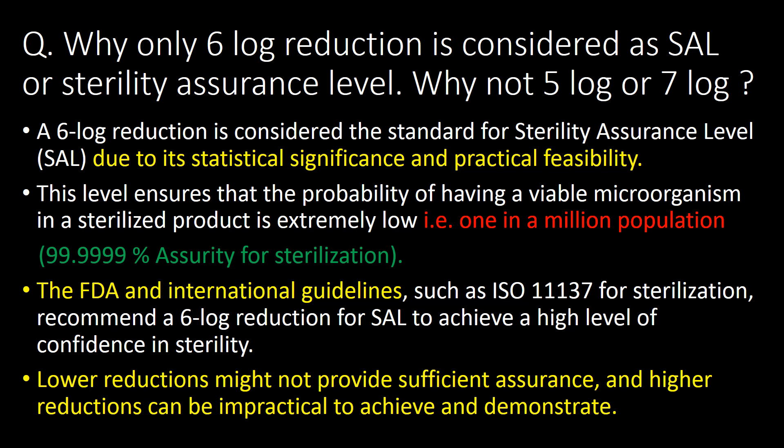The third point is guideline reference. The FDA and international guidelines such as ISO 11137 for sterilization recommend 6 log reduction for sterility assurance level to achieve a high level of confidence in sterility. The fourth important point is that lower reductions might not provide sufficient assurance, and higher reductions can be difficult to achieve and demonstrate.